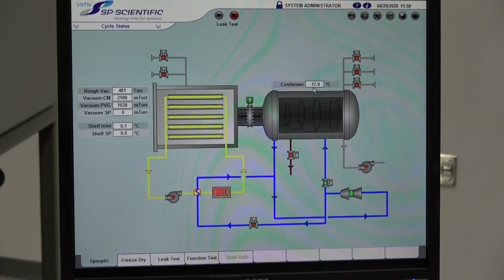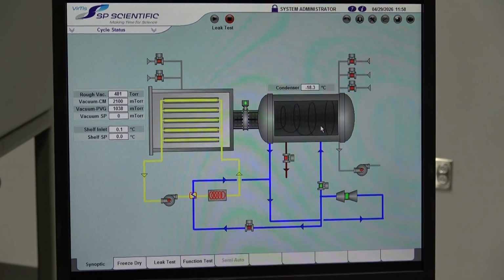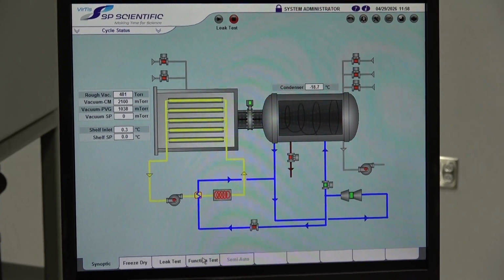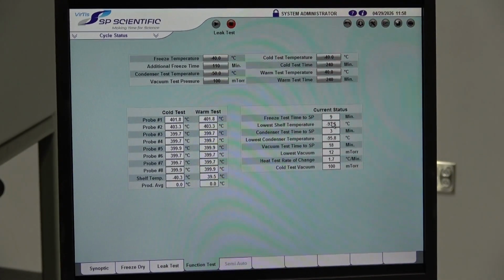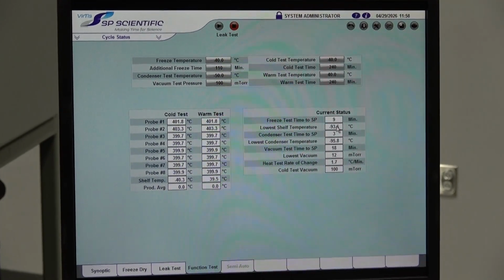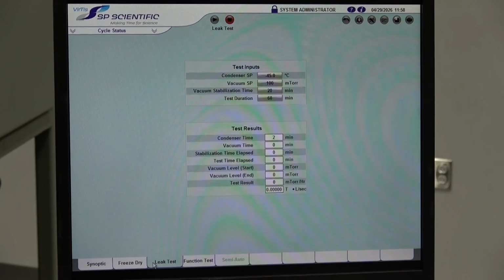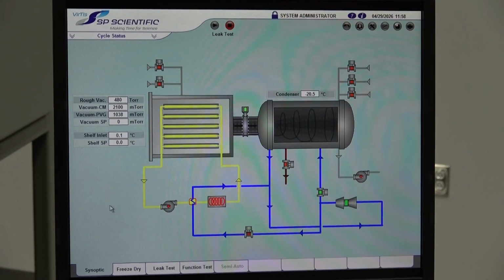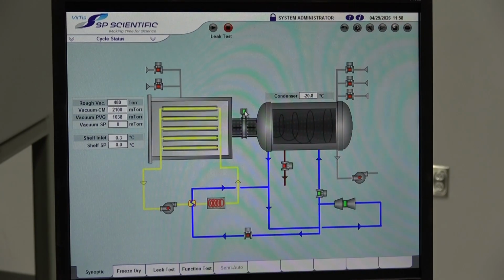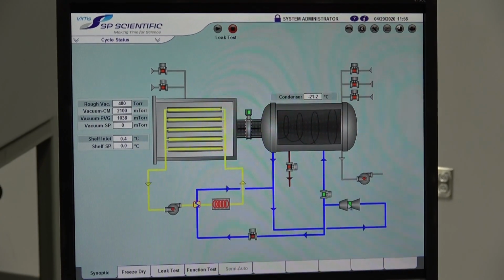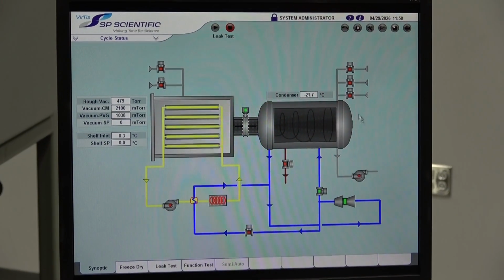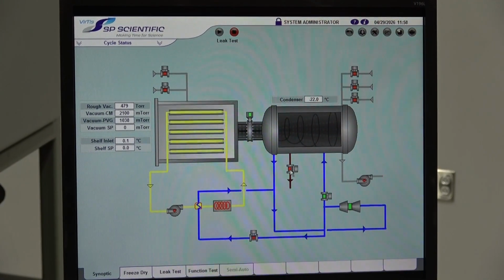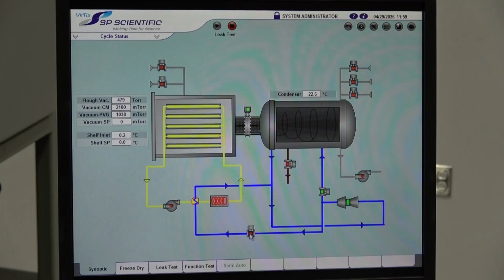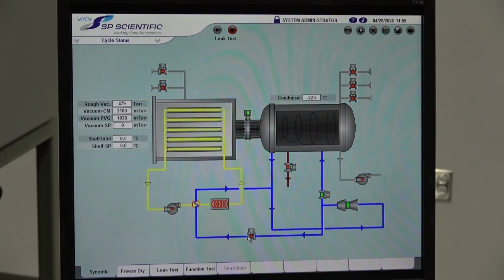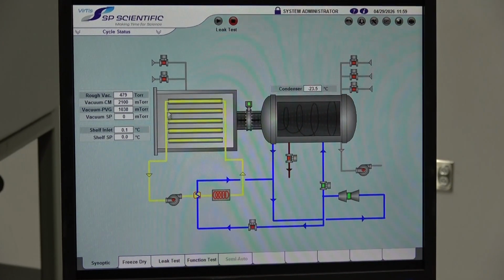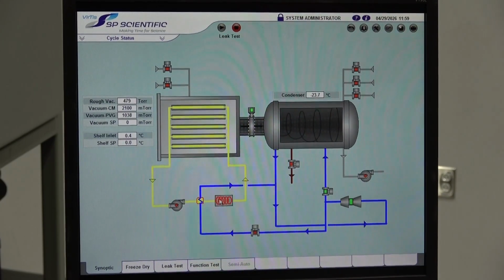Just a real workhorse, and it's just a big area to have to cool that condenser there, but like I said on our last function test, we were hitting some really cold temperatures with that compressor, so I was really impressed with it. But a lot of nice tools on this. You can see our isolation valve here is green, so it is shut off, and this is on here. This is our vacuum pump. This is our defrost valves. This is our drain valve. This is our valve for our circulating fluids here, and we got our circulation pump for our silicone fluids here, and we got our heater here for silicone fluids.